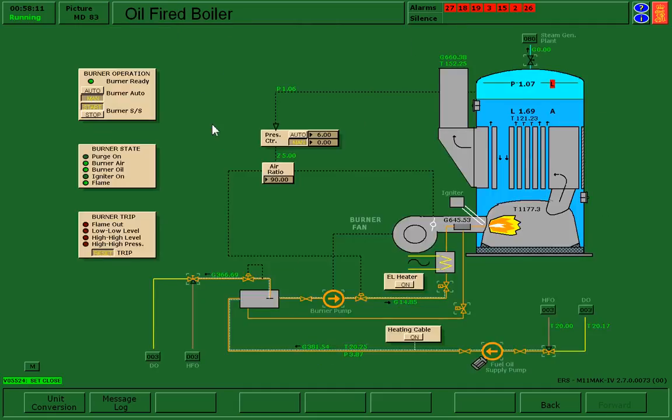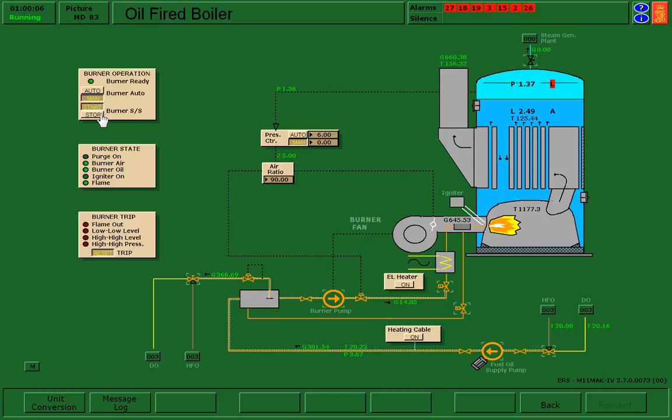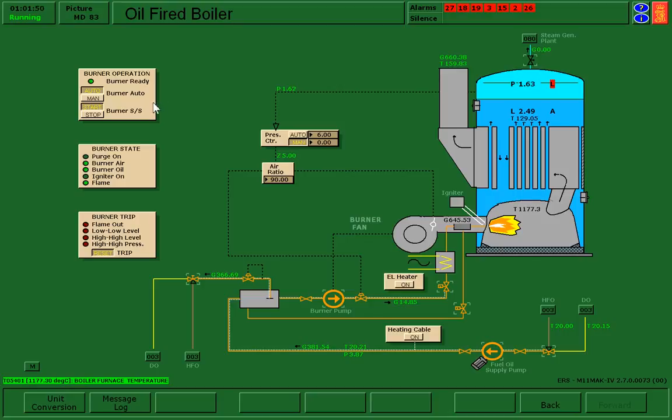Before I go and start some other process lines potentially inside the plant, I'm not quite safe to walk away from this boiler at this point. What we've left it in is the burner controls in manual. What that means is that nothing's going to decide to turn off this burner if there's a problem. It's only us that's allowed to make that decision right now. So we're going to switch our burner over into automatic mode. What that means is that if the burner itself senses that there's too high a pressure inside the boiler, it's going to make the decision to turn itself off. So we've relinquished control of the starting and stopping of the burner to this device as a safety precaution.